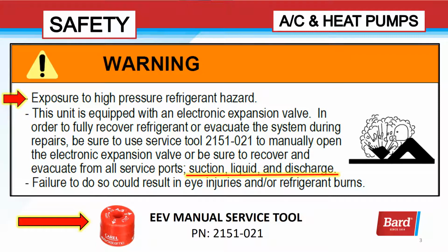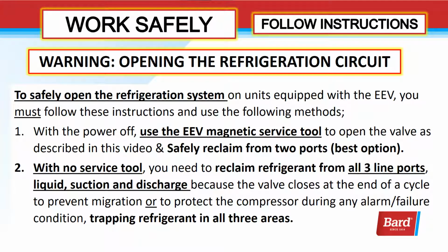If this tool is not available, be sure and recover refrigerant from all three lines, or ports. These include suction line, liquid line, and discharge line. Failure to follow the process and the directions in this video could result in eye injuries or refrigerant burns. Remember, let's work safely. To safely open this refrigeration system on units equipped with the EEV, you must follow these instructions and use the following methods.